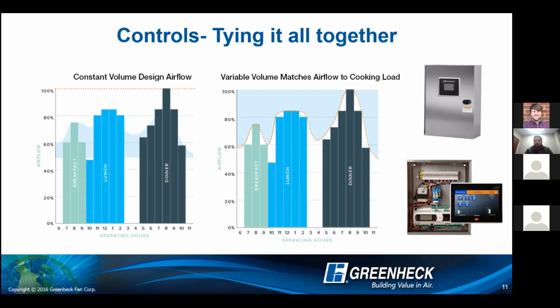The other question that I'll get quite a bit from engineers is, hey, I'm doing a school. I'm just going to do constant volume controls. It's super easy. We're just going to turn this thing on. It's going to run at 100%, and away we go. What I would contend that you should keep in mind is that typically, let's say we're doing a pretty constant application, like a school or a university. If you have a constant volume system, let's say that system is designed at 3,000 CFM and it's constantly going to run at 3,000 CFM, the long-term energy cost of that constant volume is going to be way higher than having a system sized for a variable volume system.